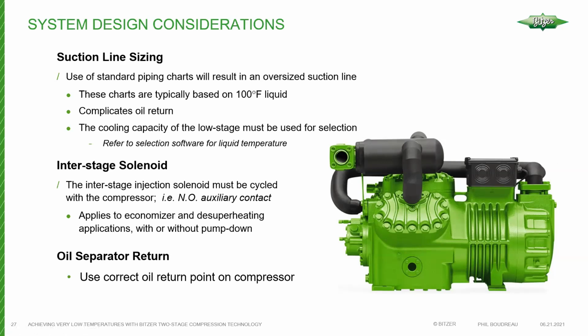And we know what happens with oversized suction lines. Oil return is not very good, and this can create a lot of problems. When oil return is not good, and you've got compressors that are direct suction, and that oil is able to accumulate in the low side, and then maybe we go on defrost at some point in time, now all that oil is going to come back in a significant volume, and it's very dangerous for compressor operation.